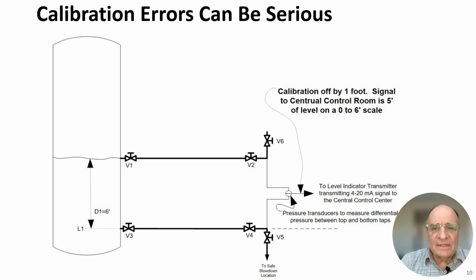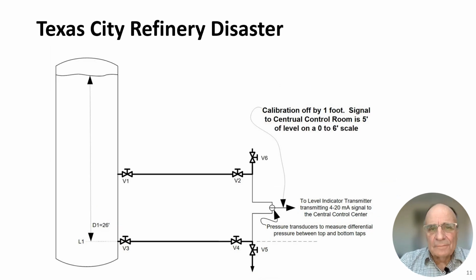Calibration errors can be a significant problem. Let us say that this is 6 foot here, from here to here, and you're in the control room maintaining 5 foot, but in actuality, the level is 6 foot. Now, you don't know it's 6 foot, so you think you still have another foot before you get to this point. Well, this can certainly give you a significant concern. On the next slide, we'll show you why.